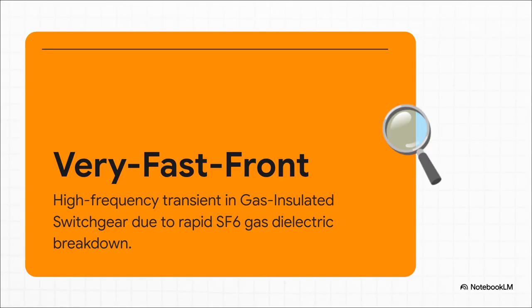By the time a conventional mechanical relay even begins to react to a fault, an FFO has already peaked, dealt its thermal and dielectric damage to your transformer winding, and completely dissipated. And pushing into the absolute fastest transients, we have the very fast front overvoltage. Now, this is a highly specialized threat.